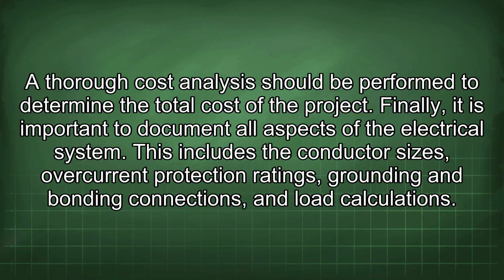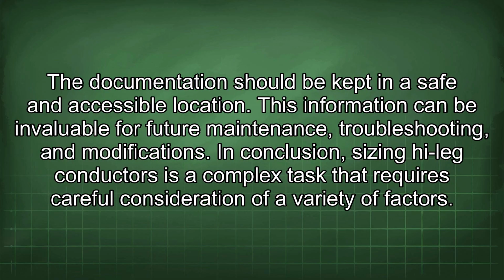Finally, it is important to document all aspects of the electrical system. This includes the conductor sizes, overcurrent protection ratings, grounding and bonding connections, and load calculations. The documentation should be kept in a safe and accessible location. This information can be invaluable for future maintenance, troubleshooting, and modifications.